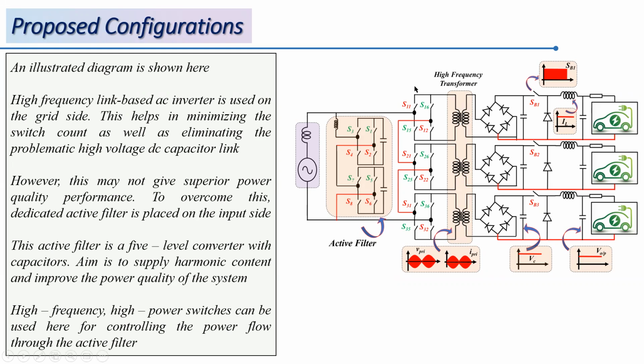Further illustration is shown here. You can see that on the input side of the medium frequency transformer or high frequency transformer, we are using an H-bridge consisting of bidirectional switches, and what it does is it converts the 60 hertz AC into high frequency AC, so that it can be passed through this medium frequency high frequency transformer. But the problem that we would be facing, as I have shown in the simulation results as well, is we would be getting inferior power quality performance on the input side too. So to avoid it, we are placing an active filter to eliminate any power quality issues, and the power rating of this active filter is equal to the harmonic content of the grid current. And since we are using only a 5 level converter on this side, we can utilize the advanced silicon carbide or gallium nitride switches to realize this active filter.